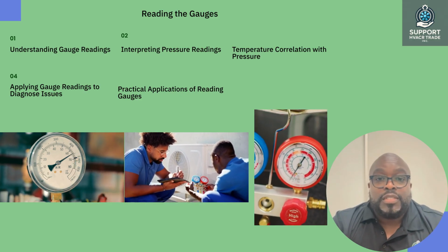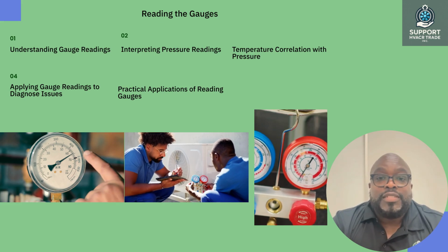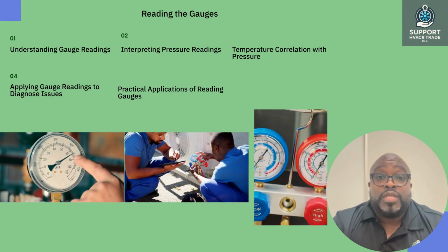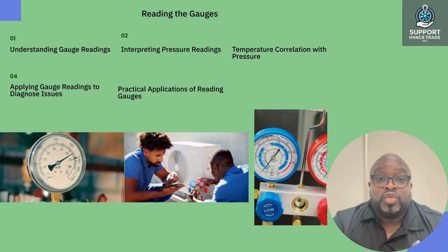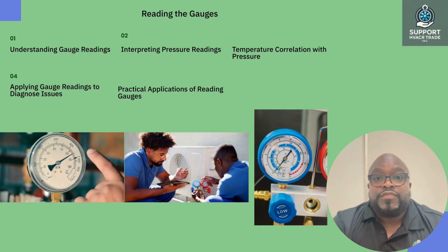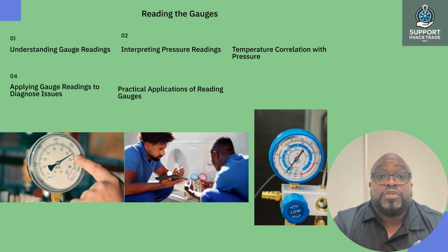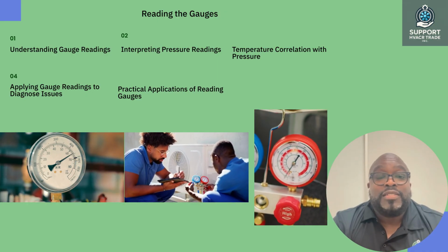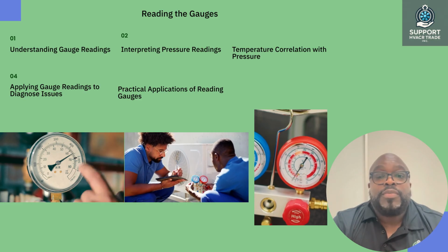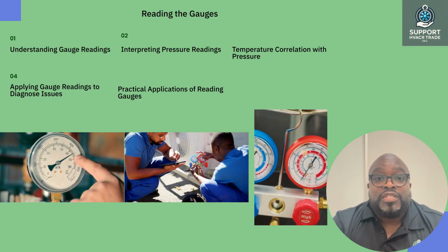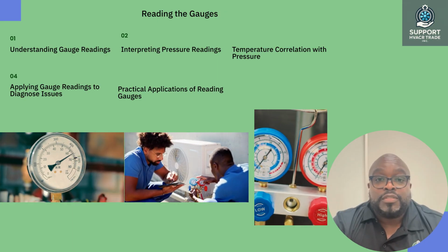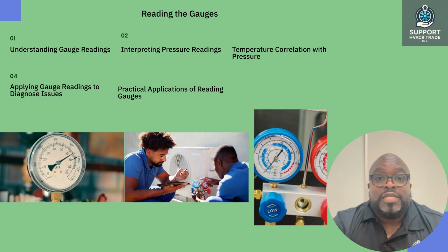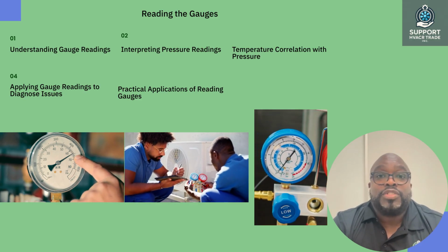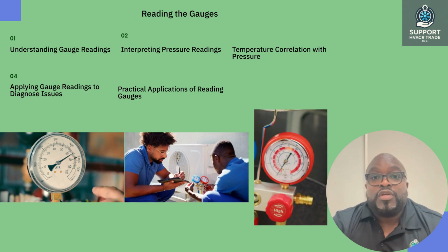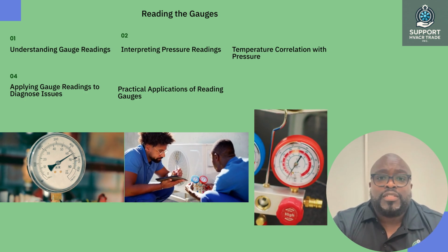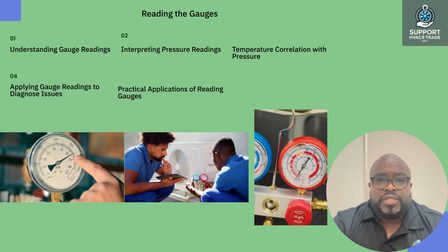Interpreting pressure readings. To effectively diagnose HVAC systems, it is essential to understand how to interpret both high-pressure and low-pressure readings. Normal operating pressures: familiarize yourself with the normal pressure ranges for the specific refrigerant used in the system. Each refrigerant has its own set of standard pressures at various temperatures. Identifying issues: use the pressure readings to identify potential problems. If the high-pressure gauge reads significantly higher than normal, it may indicate a blockage in the system or an overcharge. If the low-pressure gauge reads lower than standard, this could suggest a leak or insufficient refrigerant levels.